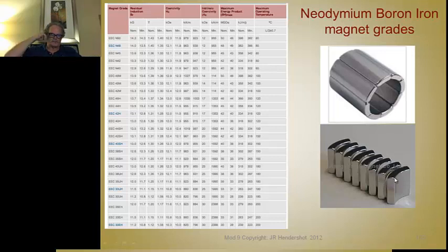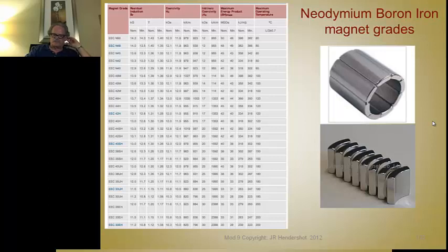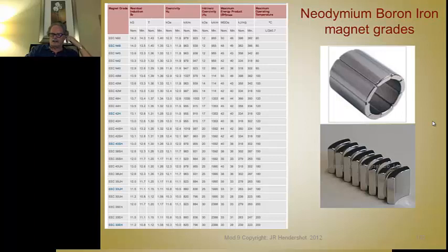Here's a picture of neodymium magnets — that's how they typically come, sintered. If they're not coated by the manufacturer, they're going to rust and your rotor will fail. If you glue a neodymium magnet to a rotor core that has not been conformally coated with nickel plating or epoxy, it's going to rust under that adhesive and the magnet will come loose. You must always purchase neodymium magnets coated. You can grind them but it's dangerous — if you grind coated magnets after gluing, be very careful that corrosion doesn't start during grinding.